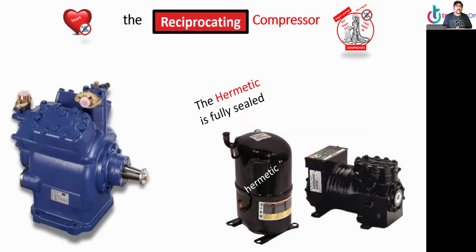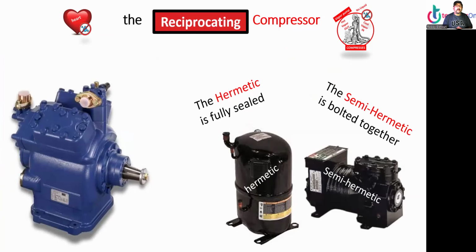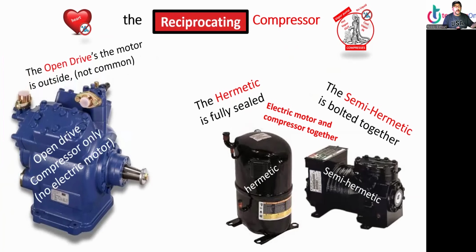The reciprocating compressor, the fun stuff. Reciprocating, first, we have the hermetic, which is fully sealed. And we have the semi-hermetic, which is bolted together, and the electric motors are inside the compressor. And we have the open drive, with electric motors outside. Not very common. I only saw it once, broken, somewhere. I'm sure it's out there. They still have them brand new, but not very common. It's belt-driven or direct drive. At least if you see it out there, you know what it is.